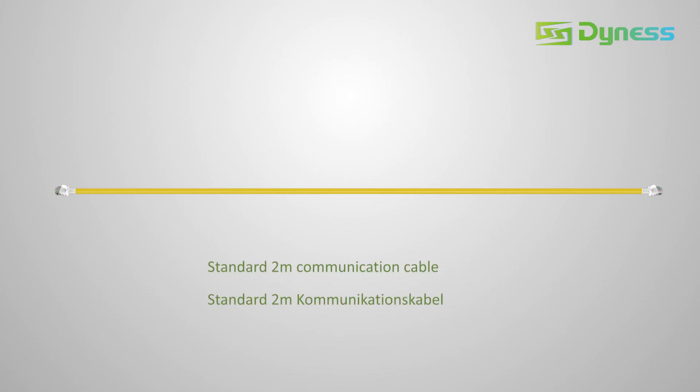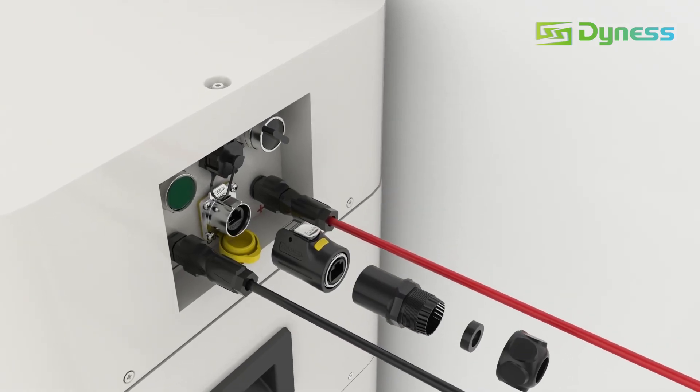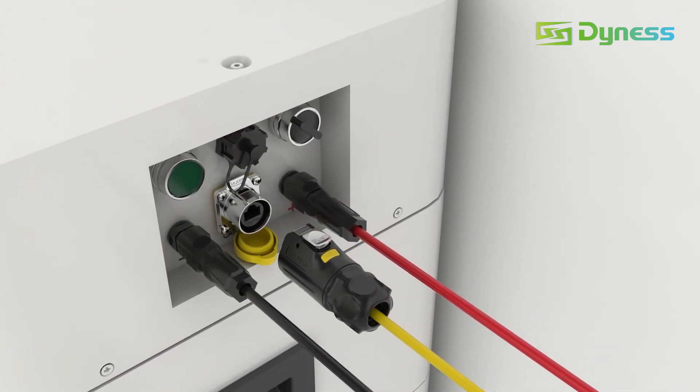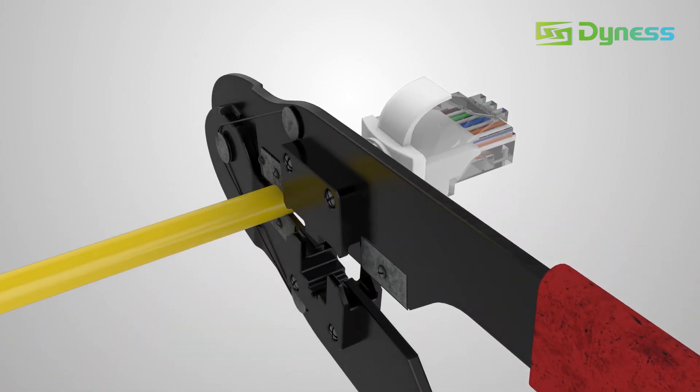Dyness has prepared a standard 2 m communication cable. Disassemble the waterproof connector. Insert the RJ45 plug into the connector, then reassemble the connector. Lock the connector onto the BDU. Cut off the RJ45 plug at the inverter side.